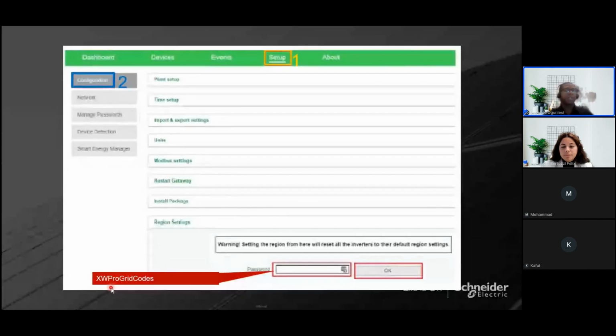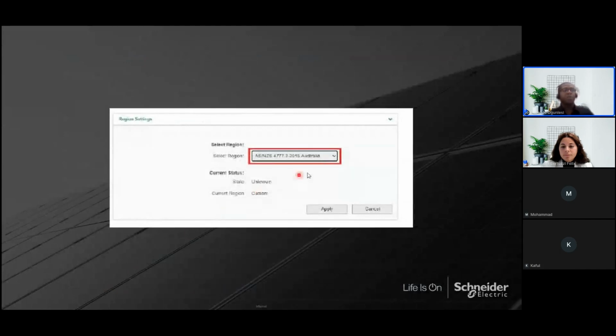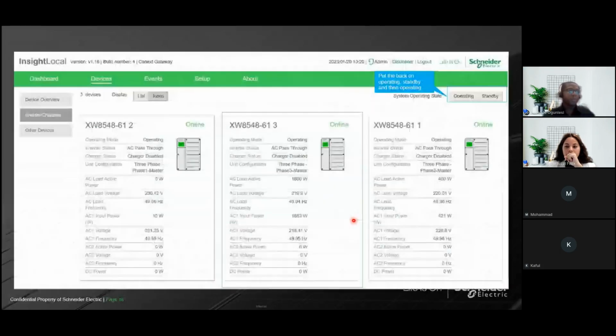But you have to input this password, and then you select your region code. So if you're in Australia, you select the Australian grid code. For the IEC, if you're in the IEC region and your region isn't specifically input onto our program yet, we also have the IEC 61727 230 volts. We have the EN 50549, and we have some other codes for the UL market. So you just select which one is applicable to you at that instance, apply, and make sure it sticks. If this isn't done, you're also going to have some very weird behavior with the system. So critically, make sure you put in the right region code.